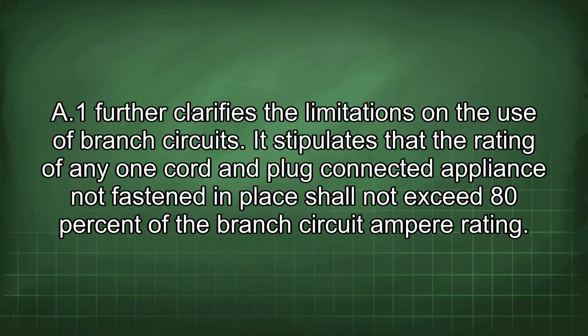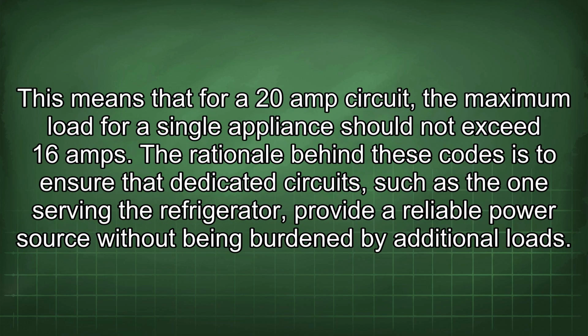It stipulates that the rating of any one cord and plug connected appliance not fastened in place shall not exceed 80% of the branch circuit ampere rating. This means that for a 20-amp circuit, the maximum load for a single appliance should not exceed 16 amps.